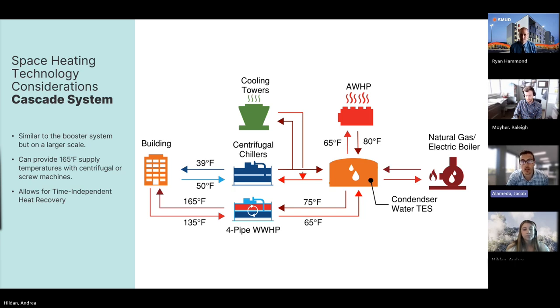And if this system was being used for a new building or a new campus, then you could use the same setup, and instead of providing the 165 degrees, you could drop that down to more modern temperatures of 130 or even 120-degree water at a higher efficiency. But in peak heating moments, where there isn't enough heat from your centrifugal chillers to charge that tank, you can use what they call trim air-to-water heat pumps to charge that tank. And again, at very efficient temperatures.